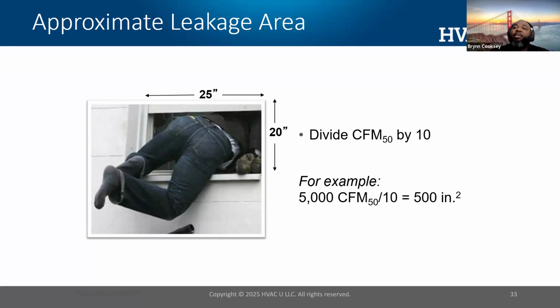So if I had a CFM 50 of 5,000, if I'm able to take that cubic measurement to square inches and divide by 10, I can therefore visualize that this house that had a 5,000 CFM 50 had a rough opening of 500 square inches, right? Roughly an opening of 20 by 25.